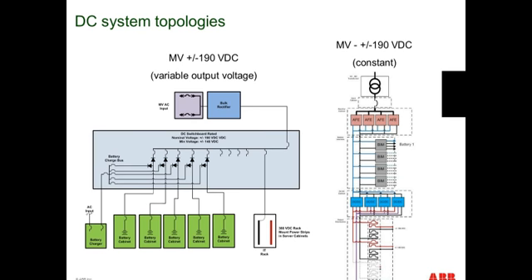If you were to take that system and make a few tweaks to it, you would get the system that you see on the right-hand side of the slide. This uses power factor corrected or active front-end rectifiers that are modular in nature, with battery interface modules that manage multiple strings of batteries. However, each string is treated as an independent entity in this type of topology. And you'll see an extra conversion phase down here, which is a DC to DC converter. In this system, the bus voltage on the output of the AFE varies when the batteries are discharging. However, the DC to DC converter acts as a buck and allows you to have a constant voltage output on the load side of the system.